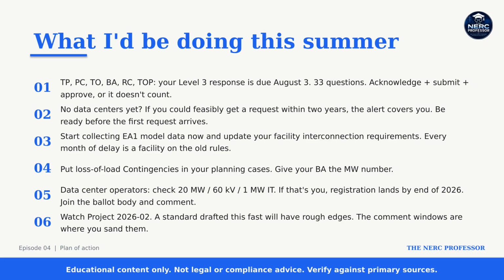2. No data centers in your footprint? The alert still covers you if you could feasibly receive a request in the next 2 years. NERC's guidance is blunt. Have this in place before the first interconnection request arrives. 3. Start collecting the Action 1 model data now and update your facility interconnection requirements. Every month you wait is another facility connecting under the old rules. 4. Put loss of load contingencies into your planning cases and give your balancing authority the number.